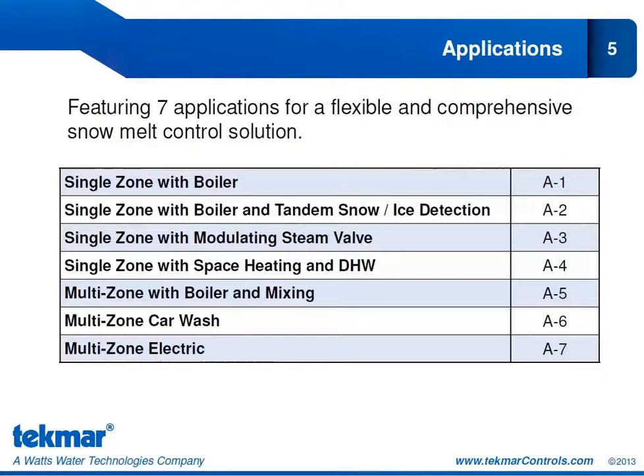So we have 7 featured applications for the 654. A single zone with a boiler. We have a single zone with a boiler and a new feature for tekmar, the Tandem snow ice detection, and we'll discuss that when we get to application 2. We can do a single snowmelt zone with a modulating steam valve. We can also incorporate the 654 into a larger system that has space heating and DHW, and we can do that because now, of course, we have the TN4 communication. We're also going to look at a multi-zone system where we have a boiler and we're doing mixing, a multi-zone car wash, and a multi-zone electric application.